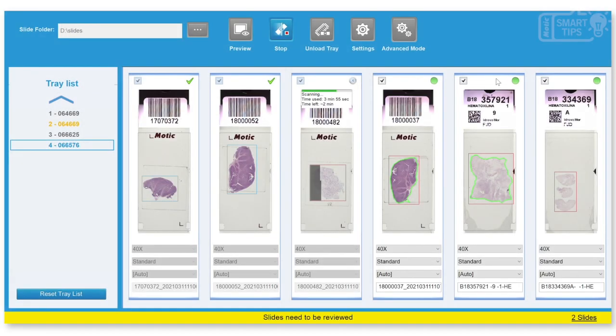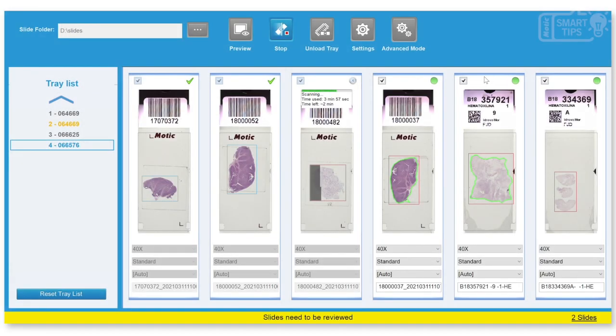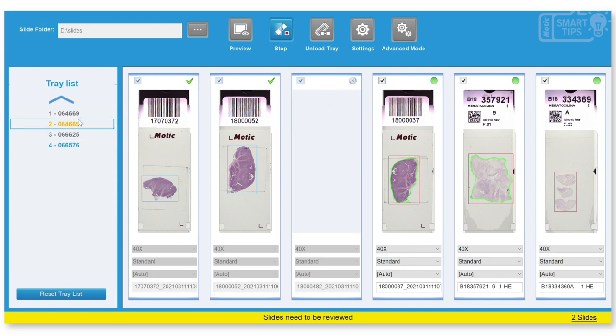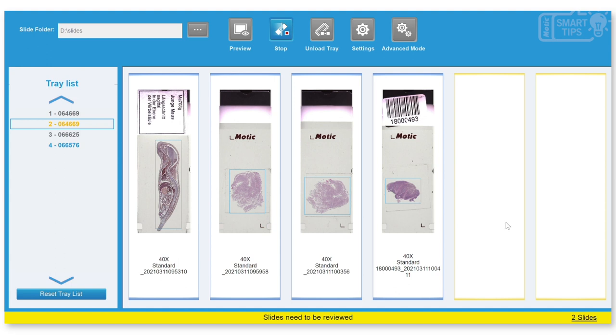Okay, so while this is scanning, I will return to the slides that were scanned first, which are the slides that we loaded. As you can see, the text appears in yellow and this is because there is important information to be reviewed in this tray. And the thing is that the last two slides were left empty, of course, purposely, but the scanner doesn't know this. So that's the reason that they appear in yellow. It's to inform you that there is something different about the slides and that you need to review it.